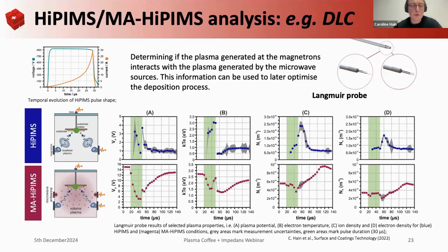There's also an option for in situ cleaning, using an impedance Langmuir probe. And of course, at some point you have to take it out and change the tip, because it will affect your values. That's why you always have to monitor whether the numbers make sense as you continue your measurements.